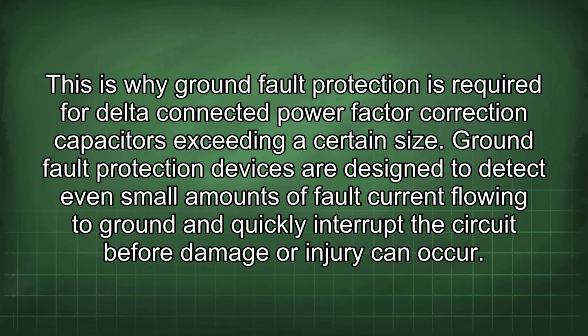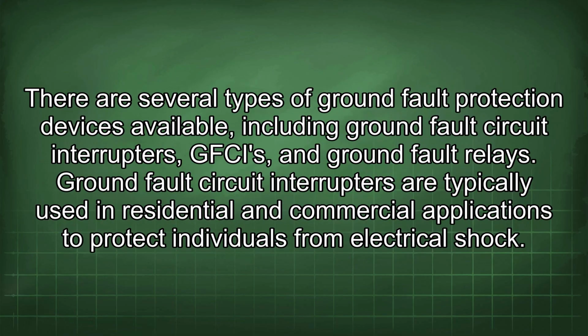This is why ground fault protection is required for delta-connected power factor correction capacitors exceeding a certain size. Ground fault protection devices are designed to detect even small amounts of fault current flowing to ground and quickly interrupt the circuit before damage or injury can occur. There are several types of ground fault protection devices available, including ground fault circuit interrupters (GFCIs) and ground fault relays.